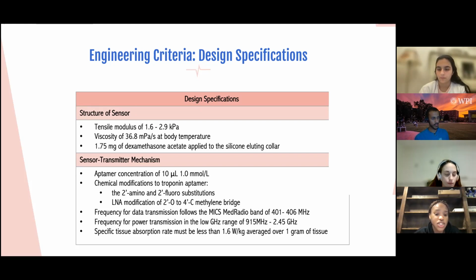Some occasional limitations that must be advised are implant migration, as well as the difficulty in obtaining long-term continuous troponin monitoring from the biosensor in a one-period insertion due to the lifespan, gradual sensor functionality loss, and stability of the biosensor. Although the expected lifespan of the device is 90 days, slight sensor failure in function can occur during this period.